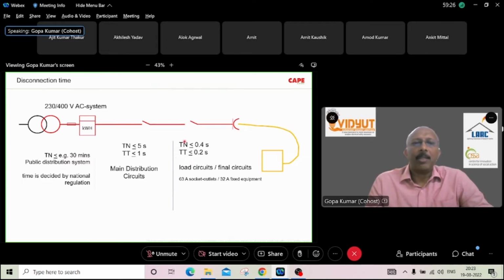These disconnection times are established in order to provide protection against electric shock. Now, if you look at protection against electric fire, or fire ignited from an electrical installation, even if the time is a little bit higher, even if the equipment is disconnected within 3 seconds, the chance of fire is nil. But anyway, the maximum allowed disconnection time is here. In the fixed part of the installation, TN system 5 seconds, TT system less than 1 second.